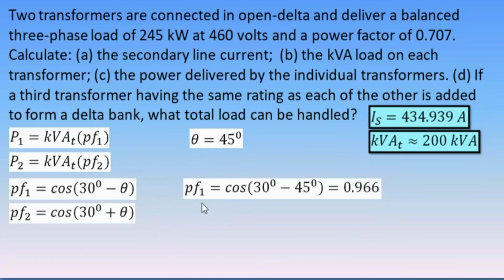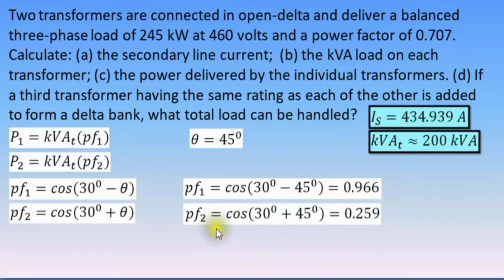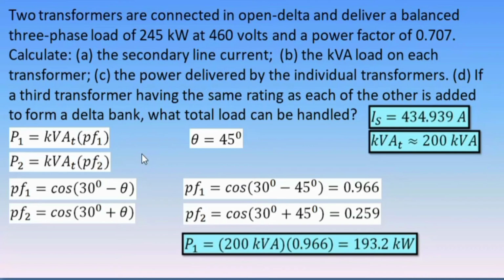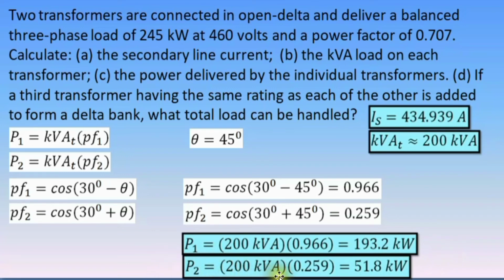equations. For the power factor of transformer 1, we have the cosine of the quantity of 30 degrees minus 45 degrees. This is 0.966. For the power factor of transformer number 2, we have cosine of the quantity 30 degrees plus 45 degrees, that is 0.259. Now that we have the power factors, we substitute them to these formulas. For the effective power of transformer number 1, we have 200 kVA times 0.966, that is 193.2 kilowatts. For transformer number 2, we have 200 kVA times 0.259.